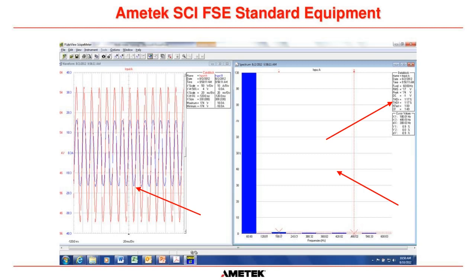If that started to go up, we may have a problem with the capacitors in the filter circuit or something we could look into. So it's an important reading to look at if you're having issues with total harmonic distortion. Okay.